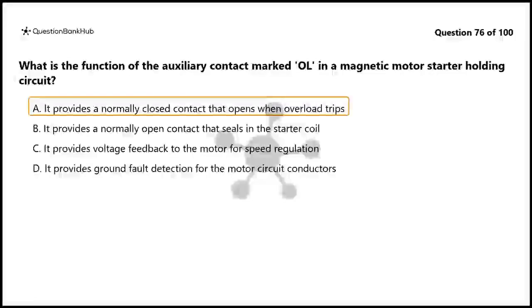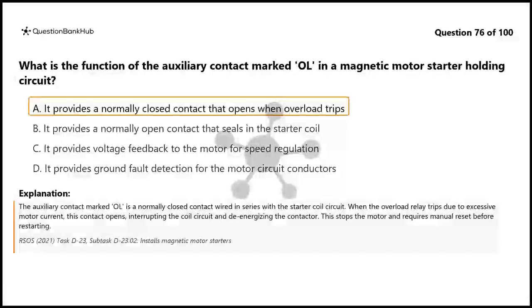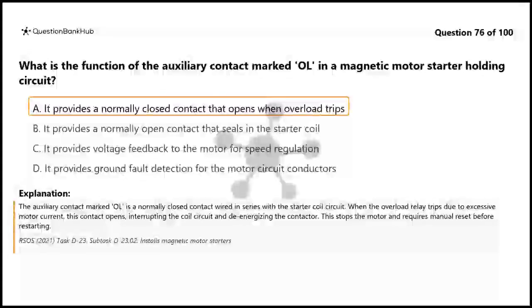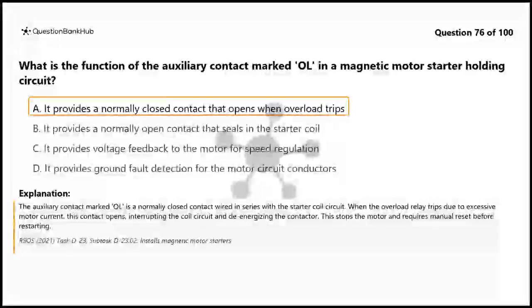The correct answer is A. It provides a normally closed contact that opens when overload trips. The auxiliary contact marked OL is a normally closed contact wired in series with the starter coil circuit. When the overload relay trips due to excessive motor current, this contact opens, interrupting the coil circuit and de-energizing the contactor. This stops the motor and requires manual reset before restarting.